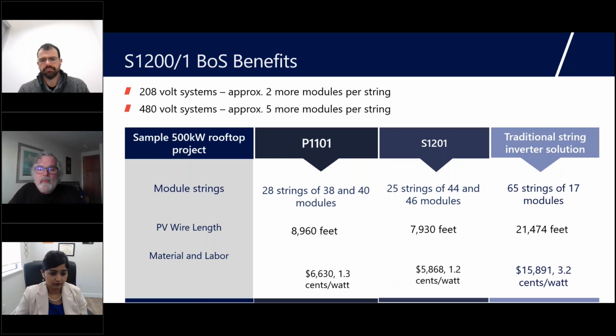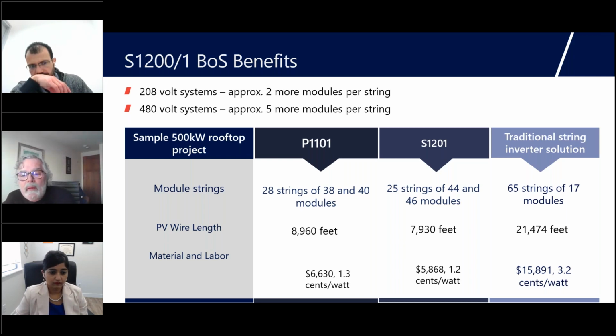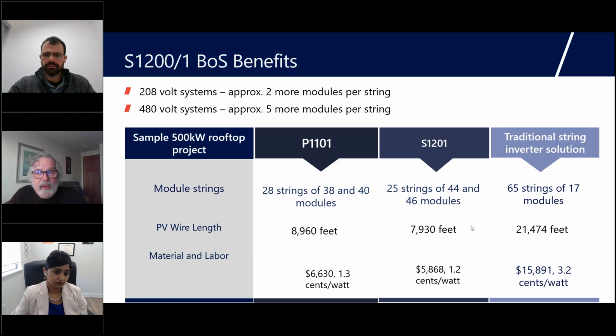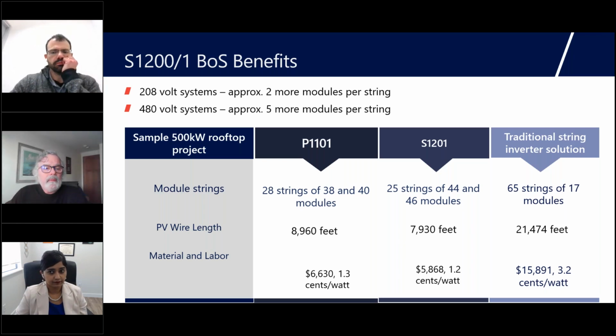We only needed around 9,000 feet of wire versus 21,000 feet of wire for the competitor. That worked out to be around $6,600 for the P1101, for PV wire and the labor required to install it, versus $15,800 for wire and the labor to install it. With the S1200, S1201, we do allow slightly more oversizing at the string level. It works out to approximately two more modules per string at 208, and approximately five more modules per string at 480. For this particular BOS comparison, we're actually able to get six more modules per string because the modules were fairly low power, around 450 watts. And the next slide, please.